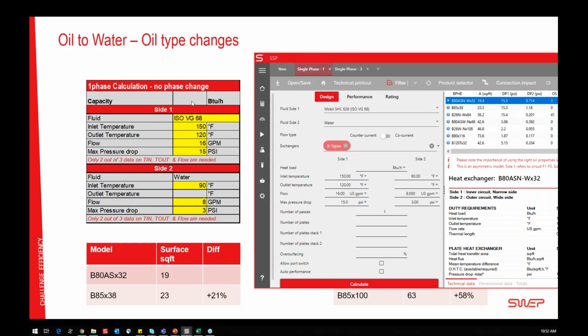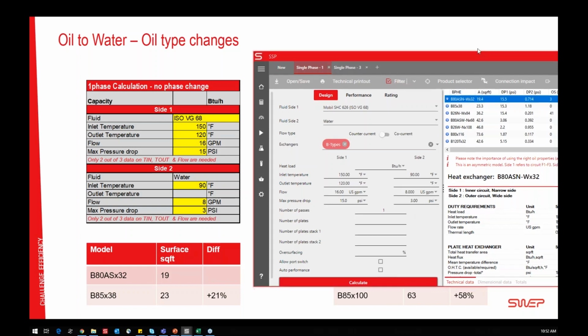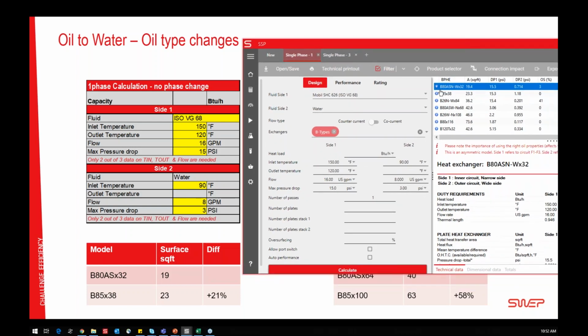So that was the oil side. In this case, we do not have a capacity, but we have an inlet temperature, a target outlet temperature, and an oil flow on the oil side, and we have a pretty hefty maximum pressure drop of 15 psi. On the other side, we have water in at 90. We don't know what the temperature out will be, but we do know that we have half the flow of the oil. And on the water side, we have a maximum pressure drop of 3 psi. So when we do the calculation, we get 2 heat exchangers. One is asymmetric and one is symmetric. The B80ASx32 is asymmetric and has a 19 square feet surface area, and the B8538 is symmetric.